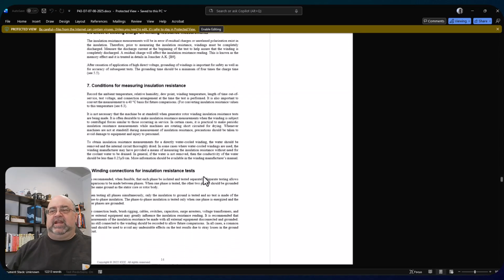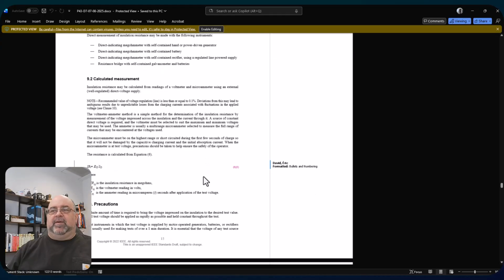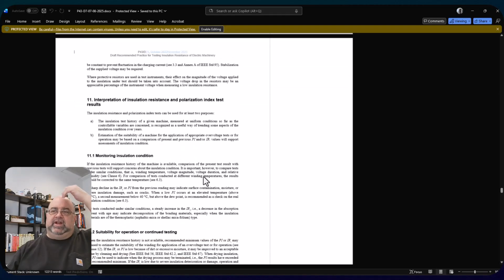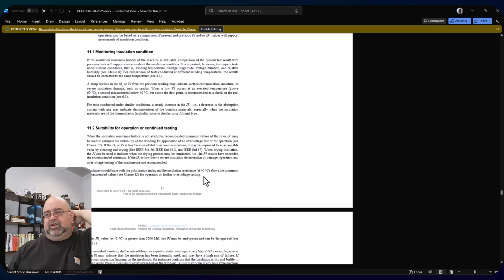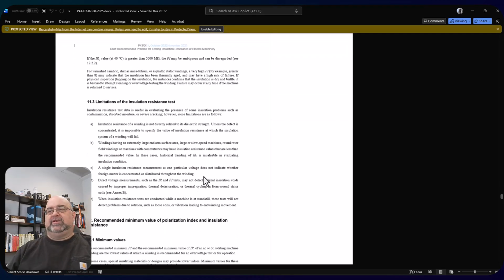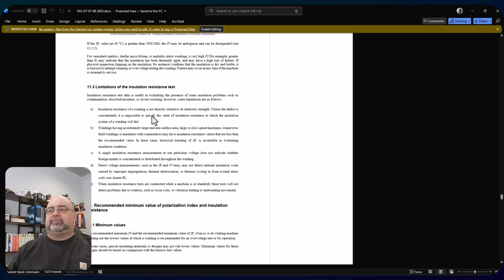We do get again into more descriptive stuff. This is how to measure it and how to interpret it. Okay, so one of the big things: insulation test data is useful in evaluating the presence of some insulation problems such as contamination, absorbed moisture, or severe cracking. However, limitations are as follows. Insulation resistance of a winding is not directly related to its dielectric strength unless the defect is concentrated. It's impossible to specify the value of insulation resistance at which the insulation system of a winding will fail.